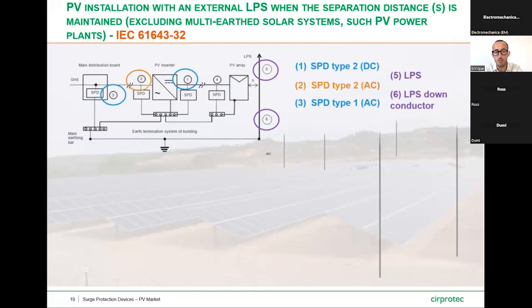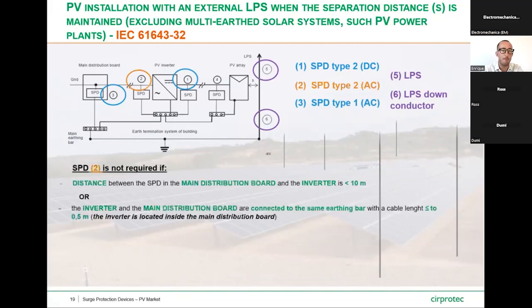In the location 2, it would need to install an SPD type 2, but this one will not be required if the distance between the SPD in the main distribution board and the inverter is below 10 meters, the same as in the previous slide, or when the inverter and the main distribution board are connected to the same earthing bar with a cable length the same or below 0.5 meter, like when the inverter is located inside the main distribution board.